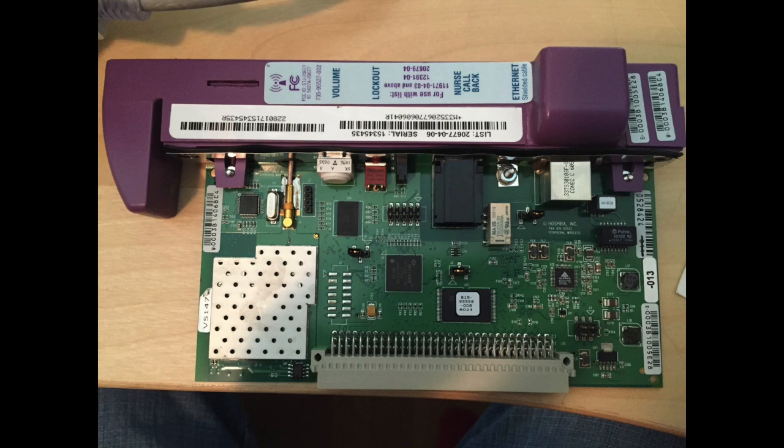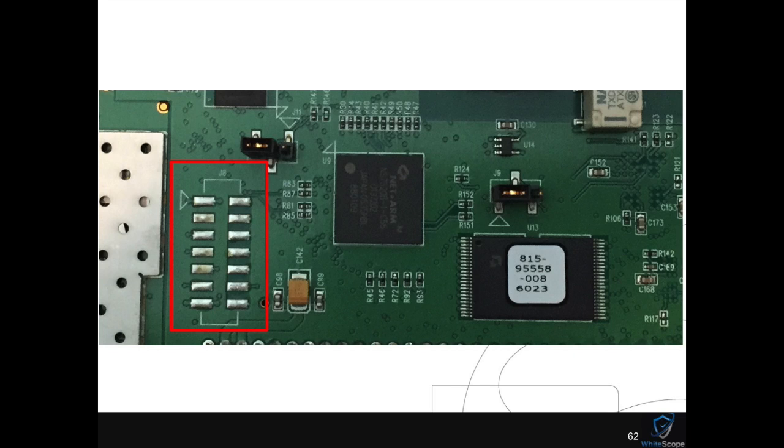And so if we take a look at what's there, we see some striking similarities between this communications module and the communications module that we looked at before. One of the primary differences is instead of having that 10-pin RS-232 cable from the communications module to the main board, we have this Eurocard connector down here that provides essentially a backplane to the main board of this pump. So that's the same processor, there's the flash, and there is what appears to be a JTAG interface as well, right? So pretty straightforward.